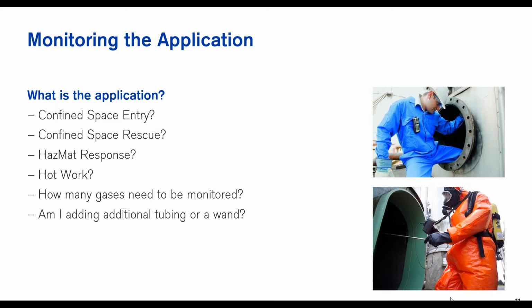Absolutely, and thank you for bringing up the hot work permit thing—NFPA 51B requires you to verify you do not have a flammable atmosphere. Unfortunately, I've had a lot of clients mention that they do a hot work permit, but they do not gas test.